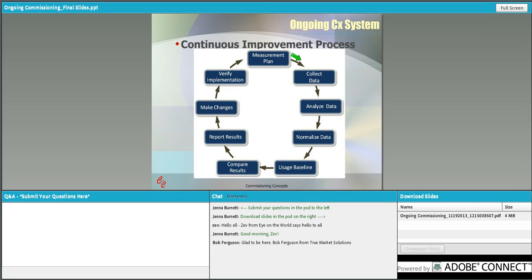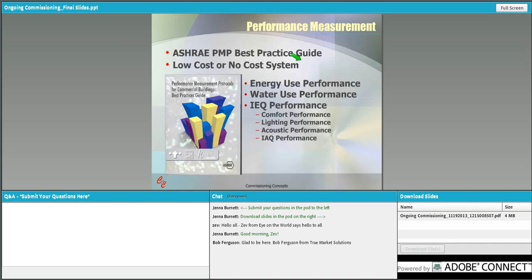The continuous improvement process is fairly simple. You have a measurement plan, you collect the data, you analyze the data, then you normalize the data, and then you compare it against the baseline, and you compare it against past results, and then you report the results to the managers, operators, and occupants. Then you decide what changes could you make to be better. So then you make those changes, and then always verify that the changes you made actually work, and then you remeasure the results, and the process starts over. It's simply a continuous loop that goes over and over and over, and normally the time period is every month. But with an automated system, you could do hourly, you could do weekly, but monthly is normal because that matches utility bills.